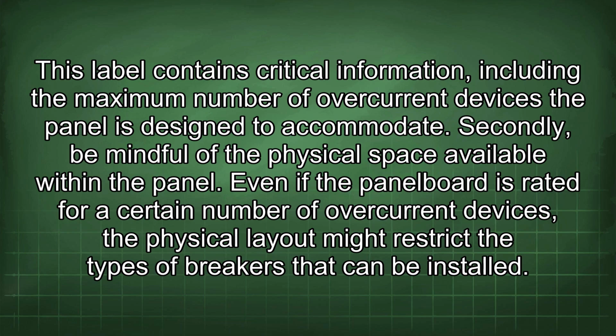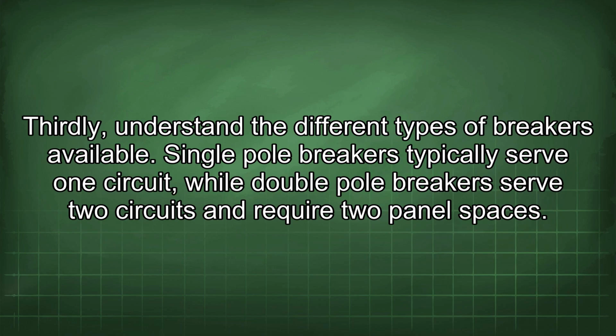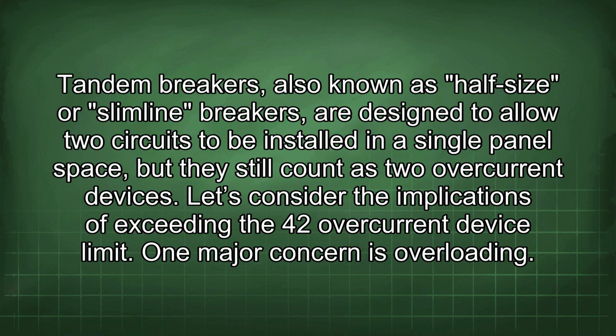Secondly, be mindful of the physical space available within the panel. Even if the panel board is rated for a certain number of overcurrent devices, the physical layout might restrict the types of breakers that can be installed. Thirdly, understand the different types of breakers available. Single pole breakers typically serve one circuit, while double pole breakers serve two circuits and require two panel spaces. Tandem breakers, also known as half-size or slimline breakers, are designed to allow two circuits to be installed in a single panel space, but they still count as two overcurrent devices.